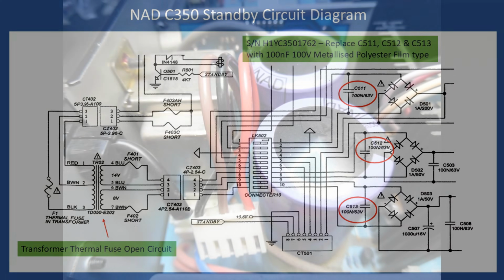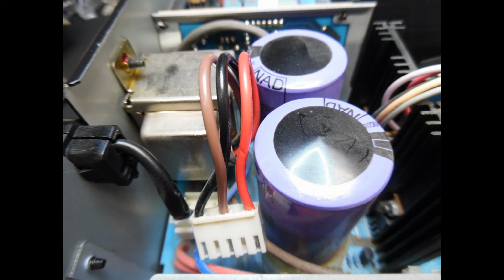So here when we look from the top, what I'm showing here is the standby transformer. You can see that it's bolted to the back panel, and what I've done is I've disconnected this 3-pin connector, and this is the primary of the transformer. And what I'm interested to learn from a fault finding point of view is to identify if the winding on the primary side is open circuit, i.e. that the thermal fuse has failed.